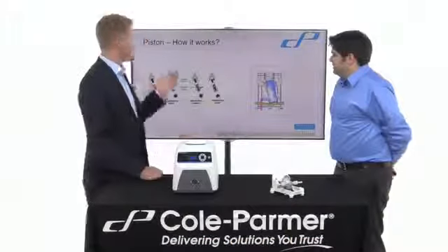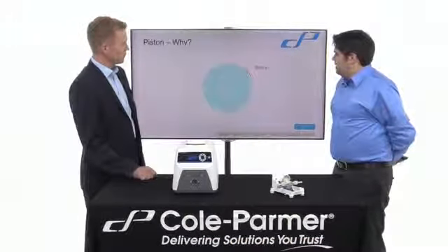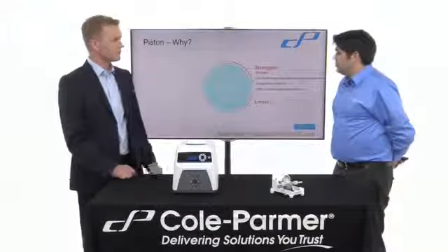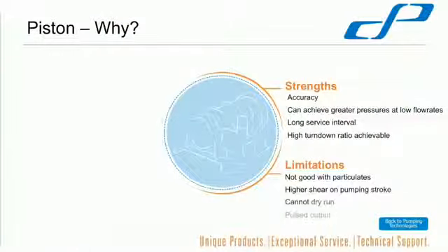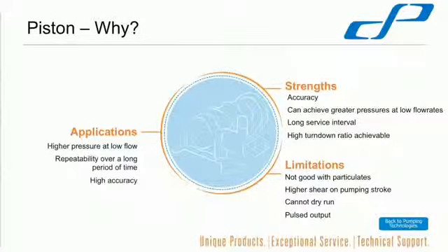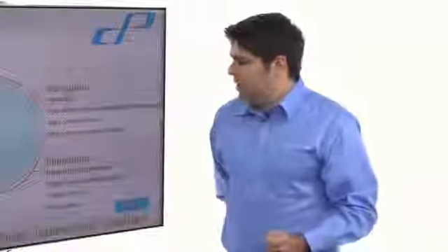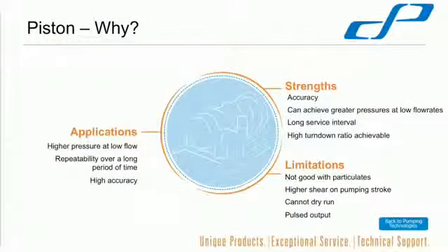So Michael, to summarise about the piston pump. Yeah, sure. Again, we mentioned some of the strengths. It's very accurate, can achieve great pressure at low flow rates, and has long service intervals. We mentioned a high turn down ratio is achievable. That means you can set it at a very low flow rate or at a very high flow rate. It's got a good range. Limitations, again similar to the gear pump, not so good with particulates. You can damage your piston. High shear, so it's not a gentle flow, it's a pulse.